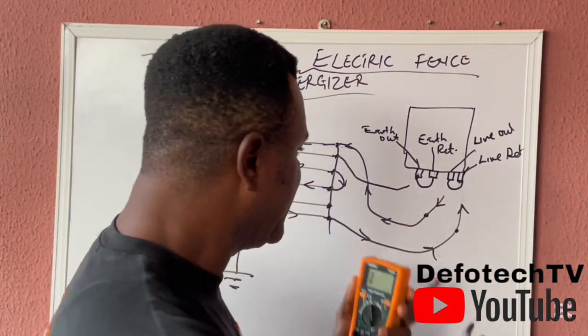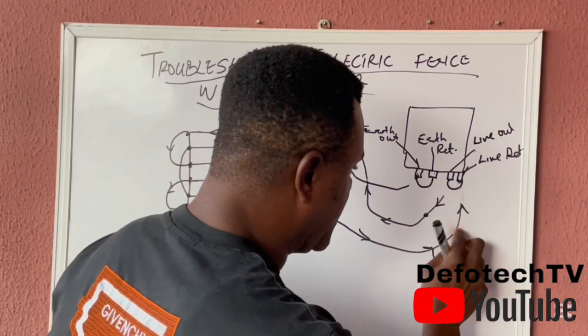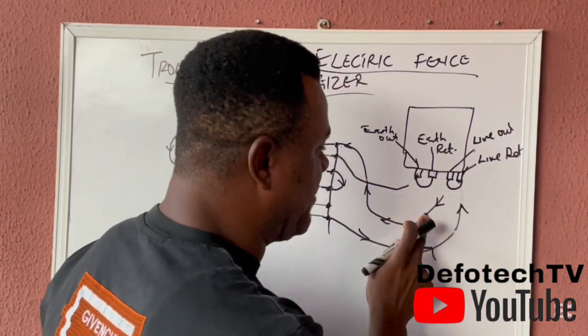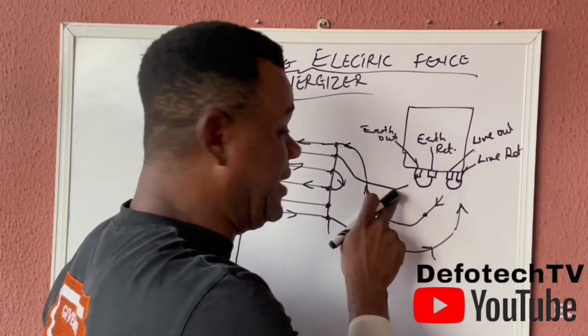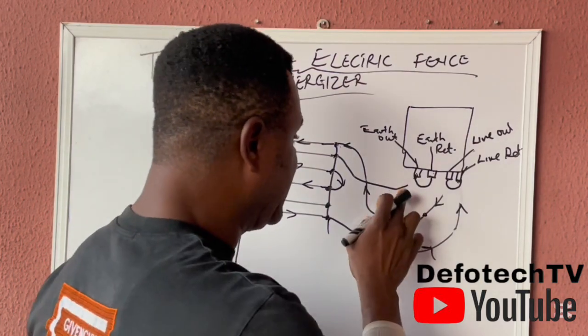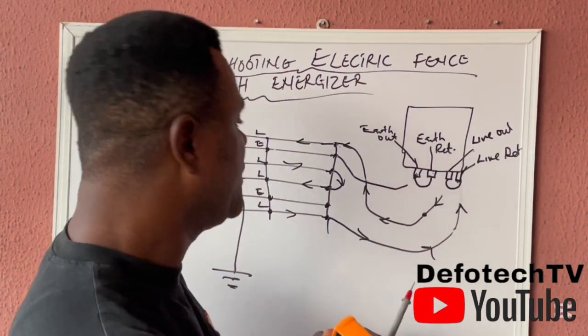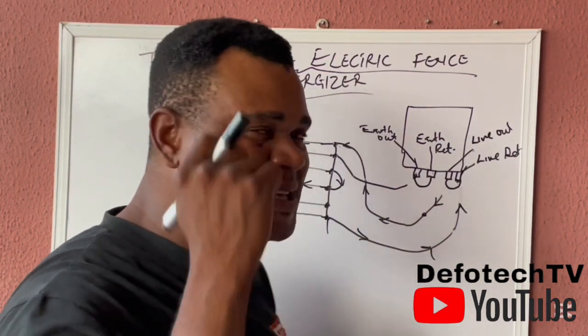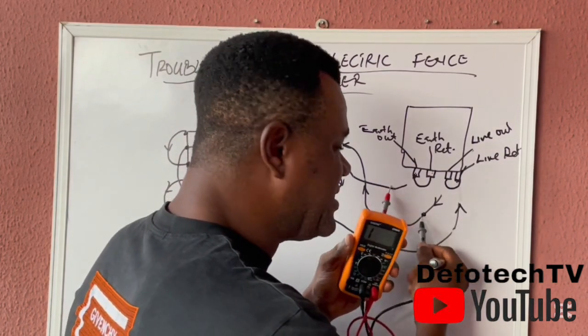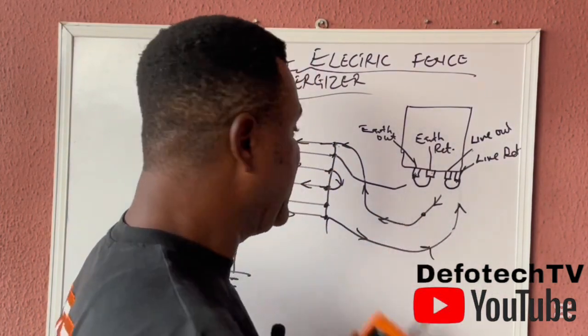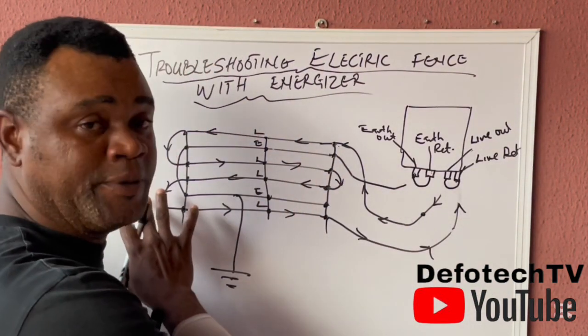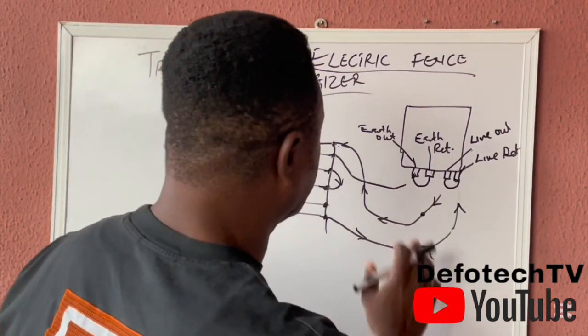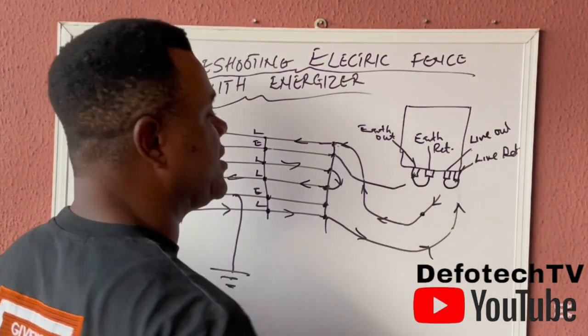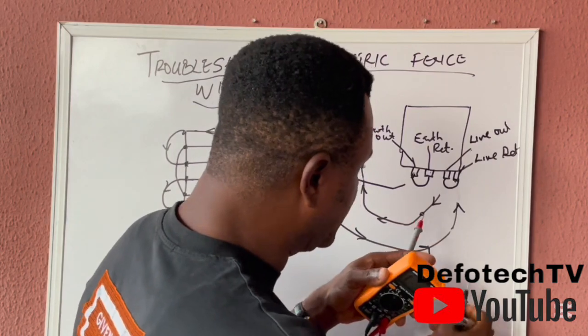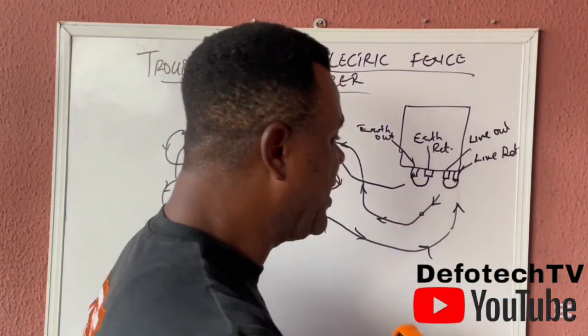Then if I take one of the probes off this, I put one here, and I put one with the earth, the cable feeding the earth, I must make sure I don't hear any sound. If I hear any sound between this and this, it means the fault is from the fence. I need to make sure that there is nothing like continuity between this and this.